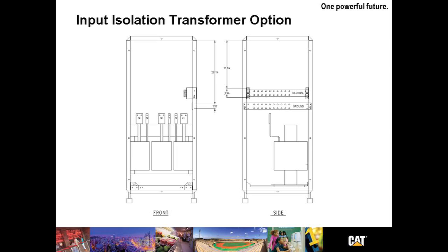It's used to provide galvanic isolation on the input of the UPS for 480 volt input systems including 480 in, 480 out, 480 in, 208 out, and 208 in and 208 out. Bottom entry or top entry is available.